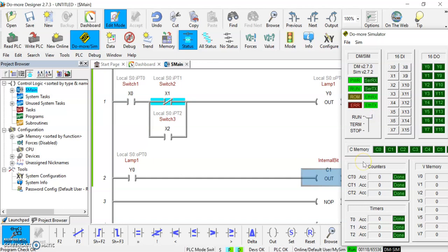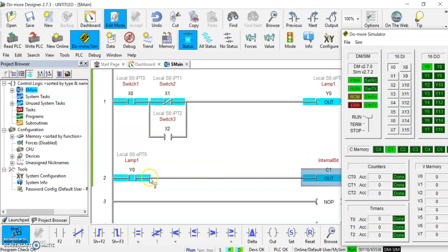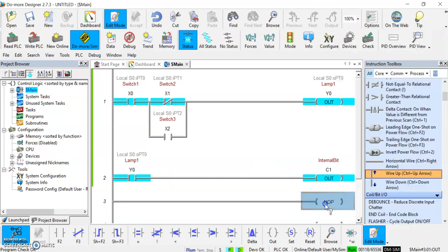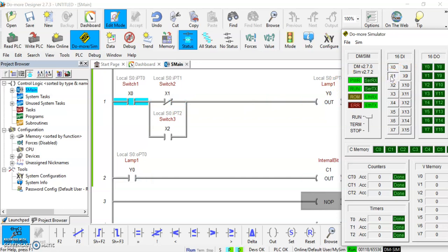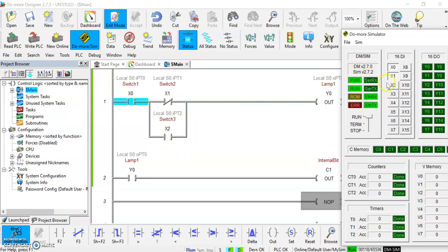Okay, now let's hit that. There we go! So we can see that Y0, our first output, lit up and it also activated and wrote a 1 here, which activated an output here in my internal bit. Let's get back to my simulator, pop that up there so you can see how that goes. If I hit X1 now, what do you think is going to happen? Well, this is going to go false and should shut everything off. So I open that up and now I have no true instruction going all the way through because this was looking for a zero, but the switch has been activated, so it's a 1. Now let's see about X2. I hit X2. So if I turn all three switches on, it should activate now. Okay, so very just a simple program there.